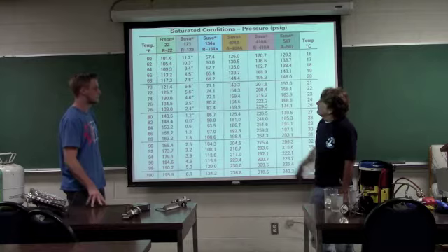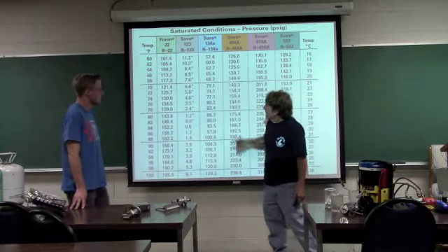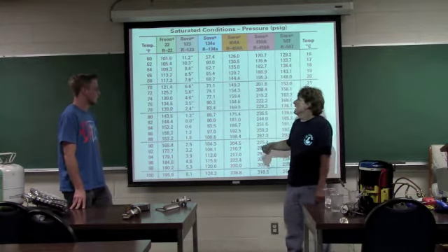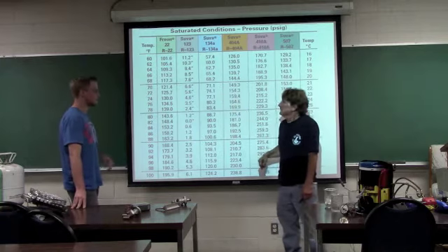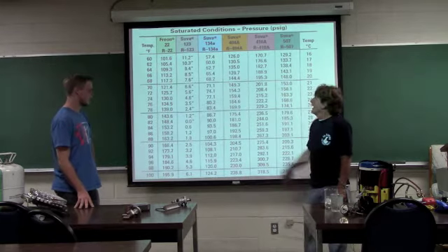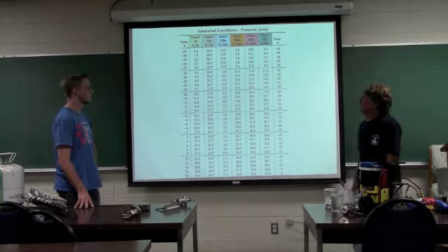So what if I have a 70 degree ambient temperature, I'm using 134A, and I have a high efficiency condenser, which I'm adding 20 degrees, so 70 plus 20, 90. So at 90, I'm at 104.3. Makes it easy. And I can do that for all these refrigerants, right? All of them. So we looked at the condenser, what about the evaporator?